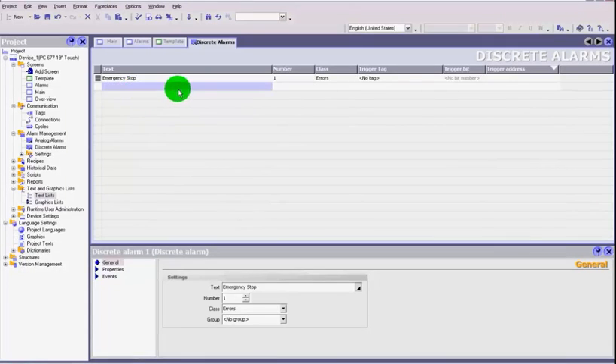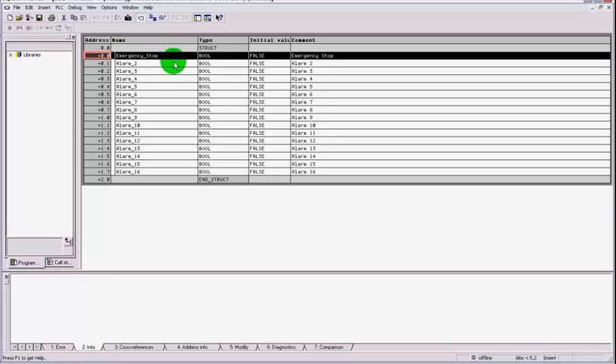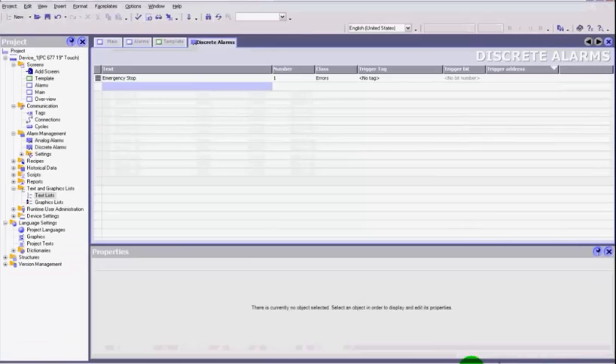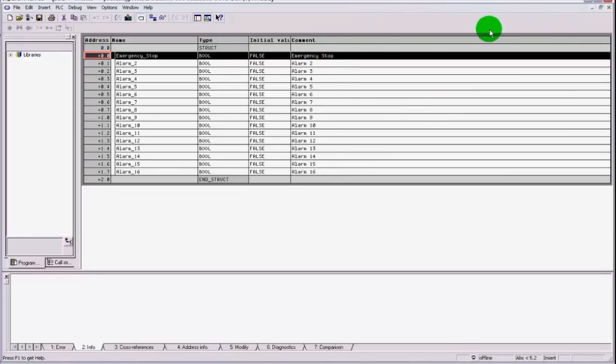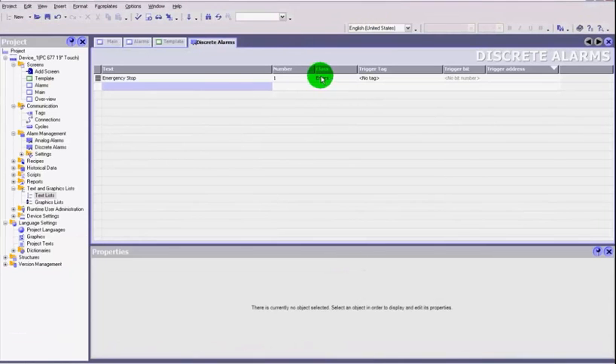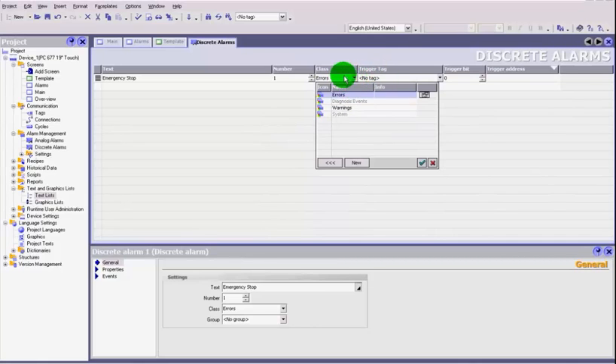The text box is what text you want to show when this alarm is triggered. We'll put in 'Emergency Stop'. If we open DB2, that's the alarm we're going to trigger. When the PLC triggers that data block bit, it sends a message to the screen to trigger the alarm connected to 0.0 in DB2. This is our trigger tag. We can add it to a class — error or warning.